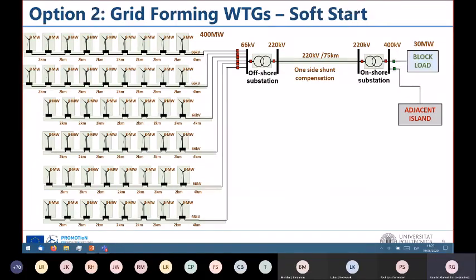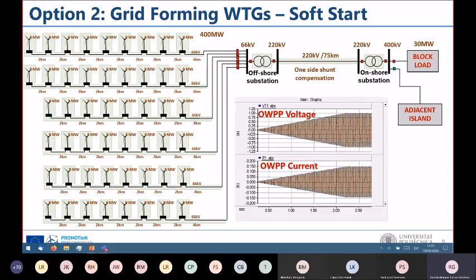The second option we have here is to use soft start. This will cover the first challenge regarding inrush currents and resonances between elements. And in this case, what we do is to power up or close all the breakers up to the onshore substation, and then bring up the voltage using a ramp.